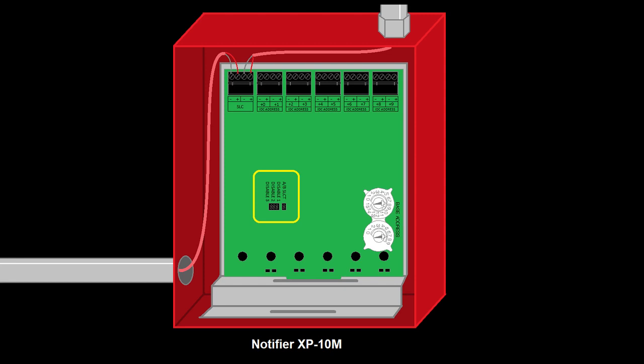There are a few other options with this card using the jumpers circled here. Instead of using 10 class B monitor points as we are, you could use five class A points by setting the A-B jumper. You could also disable the last one, two, or three module points if those points on the card aren't being used and you want to free up those addresses on the panel. From there, it's as simple as wiring each individual monitor point to the device it's monitoring on normally open contacts. In an application like this one, I recommend using a smaller gauge wire such as 16 or 18 gauge THHN rather than pulling a fire cable through the conduit. That will fill up the conduit less quickly and make for a cleaner install.